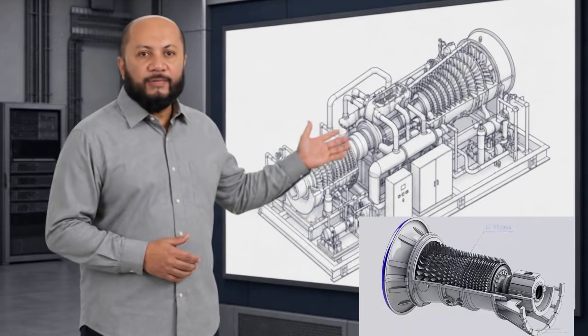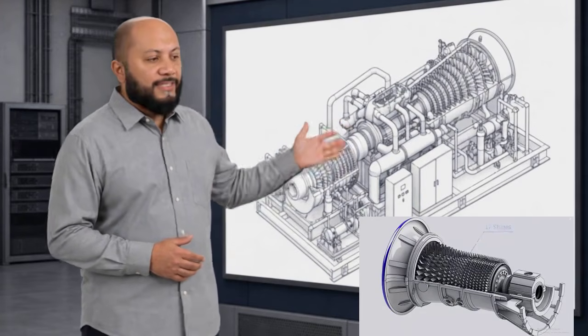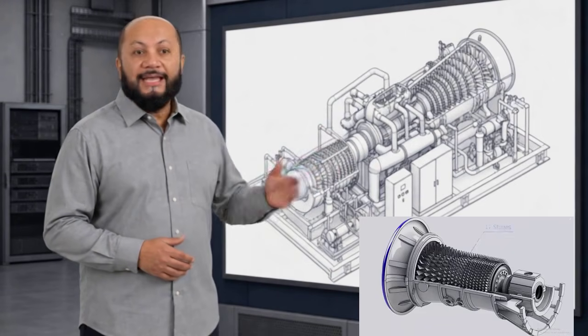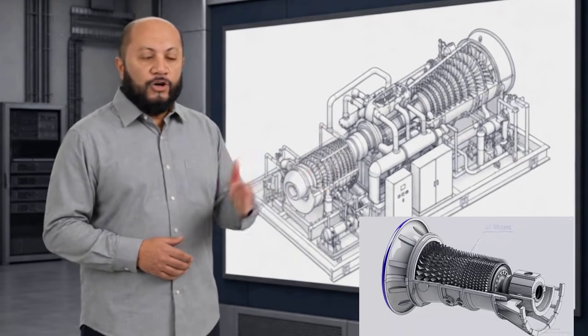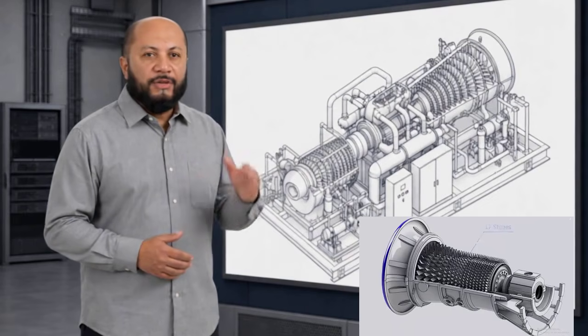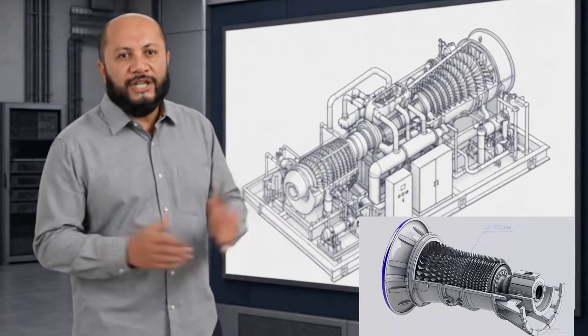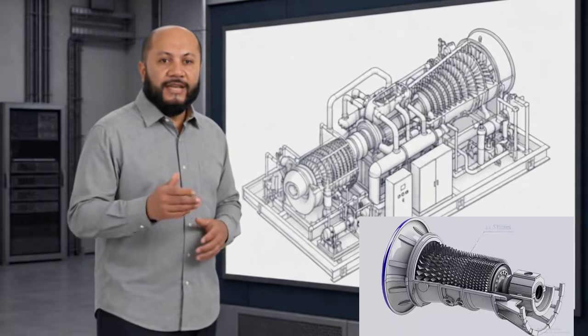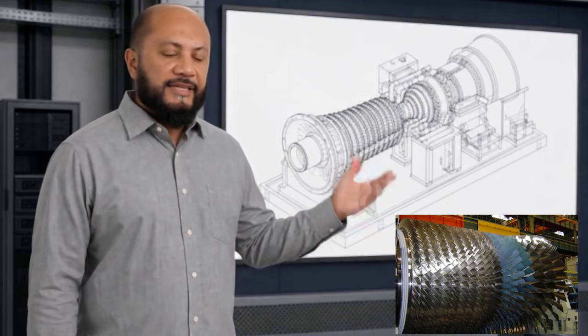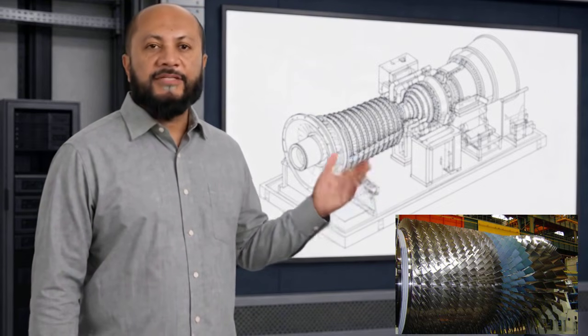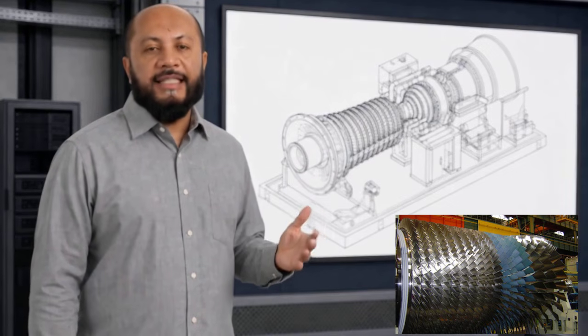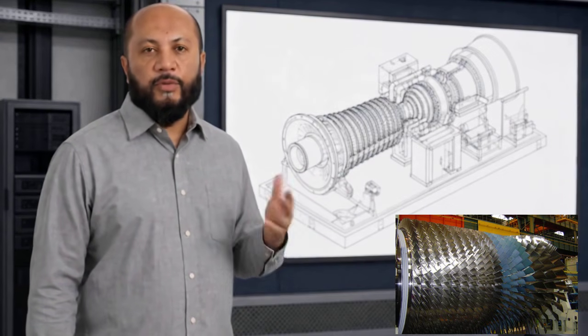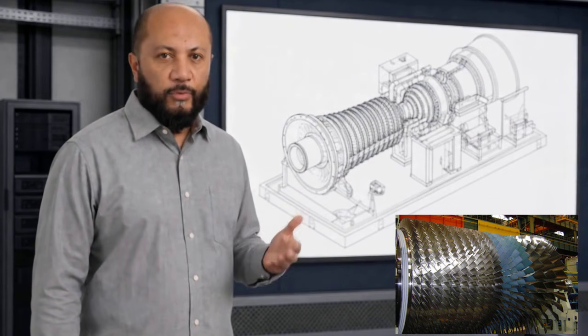The compressor includes inlet guide vanes, 17 rotor and stator stages, and exit guide vanes. The source describes the rotor as an assembly of individual wheels, stub shafts, through bolts, and rotor blades. It also notes that stages 5 through 8 use specially coated rotor blades designed to resist corrosion associated with moisture formation in that region of the compressor.